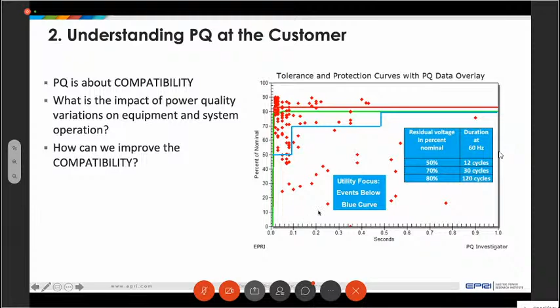Of course, a lot of voltage sags are below that, and we have to work on improving the performance for those voltage sags, or improve the ride-through characteristics of the equipment. That's what compatibility is all about. But the point is we have to understand the power quality at the customer to figure out what causes the equipment to have problems and what levels of power quality are okay for equipment operation.